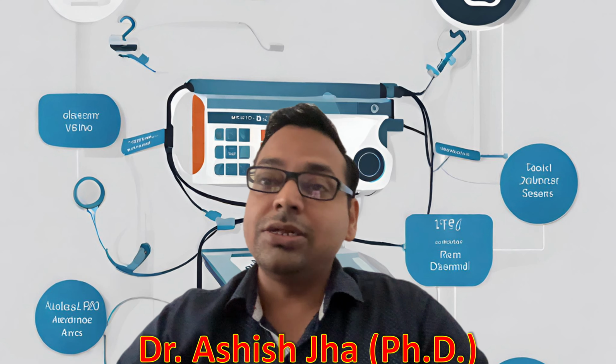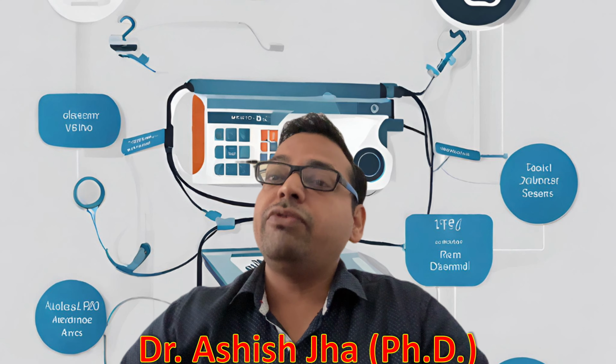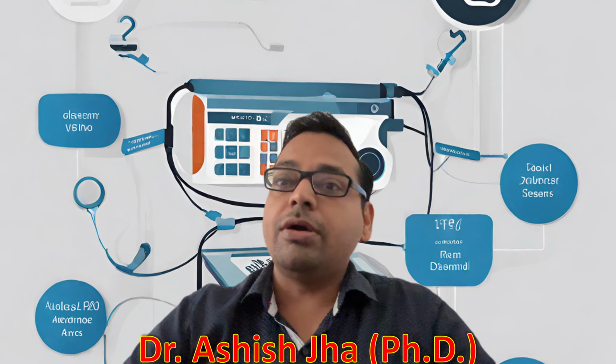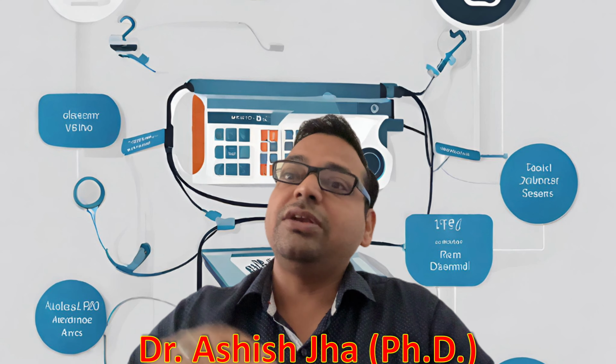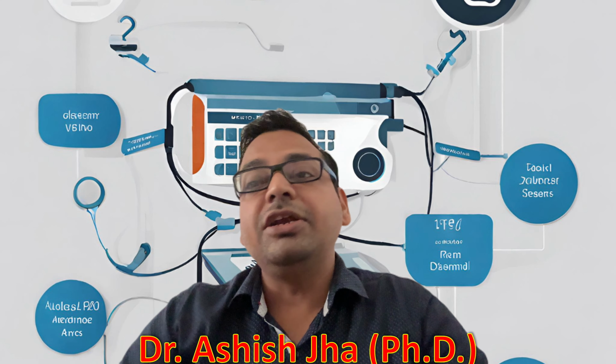So its make is very unique. It gives us a clue of which possible medical device it is, and it is very easy even in the future if we want to develop various versions of that particular medical device. Only that particular number we need to change in the whole number. So we come to know that this series of numbers of these medical devices are the different versions of this, and we get a clue of the versions also, like which version of the medical device it is.